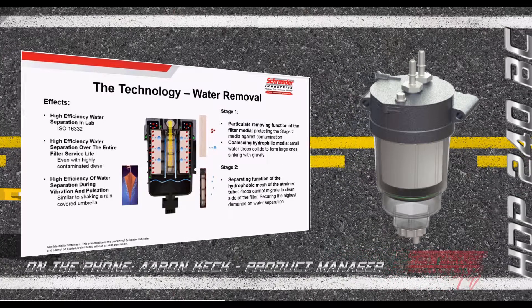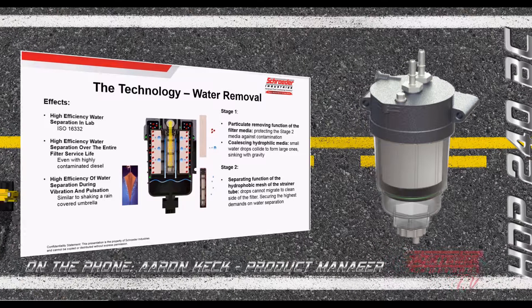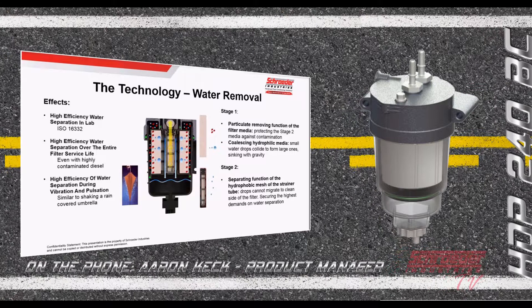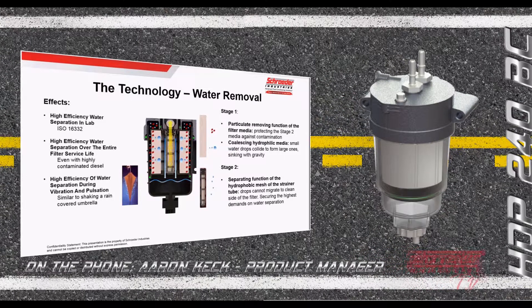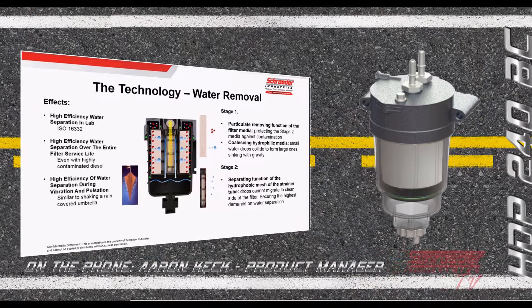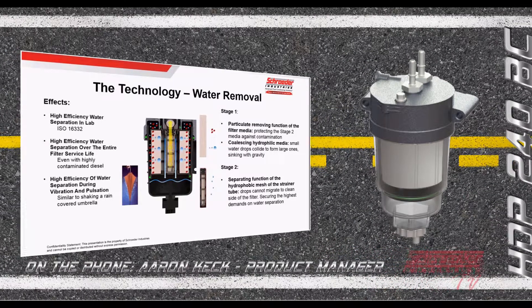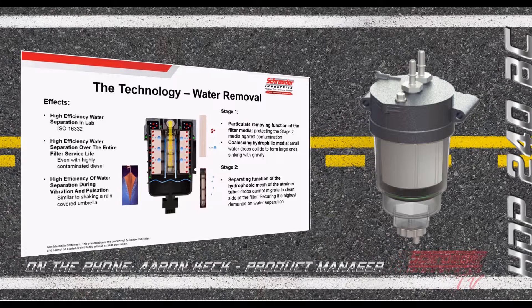In the lab we test to ISO test standards and also SAE standardized tests, measuring how clean the fuel is downstream. But we go further and look at real-world performance — where the filter must remove water while simultaneously being loaded with contaminant. Because of the way we build our filter media, we ensure high-efficiency water separation over the life of the filter even with highly contaminated diesel fuel, thanks to that two-stage approach.